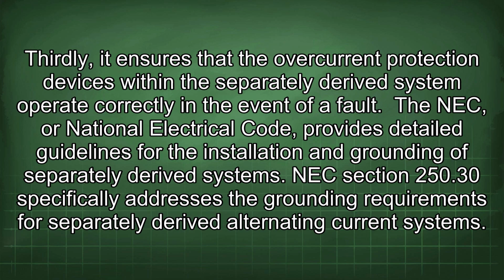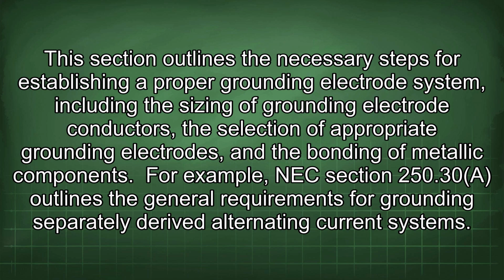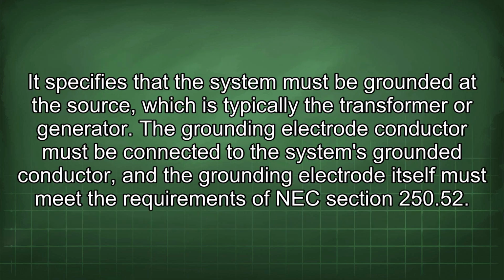The NEC, or National Electrical Code, provides detailed guidelines for the installation and grounding of separately derived systems. NEC Section 250.30 specifically addresses the grounding requirements for separately derived alternating current systems. This section outlines the necessary steps for establishing a proper grounding electrode system, including the sizing of grounding electrode conductors, the selection of appropriate grounding electrodes, and the bonding of metallic components. For example, NEC Section 250.30 outlines the general requirements for grounding separately derived alternating current systems. It specifies that the system must be grounded at the source, which is typically the transformer or generator. The grounding electrode conductor must be connected to the system's grounded conductor, and the grounding electrode itself must meet the requirements of NEC Section 250.52.